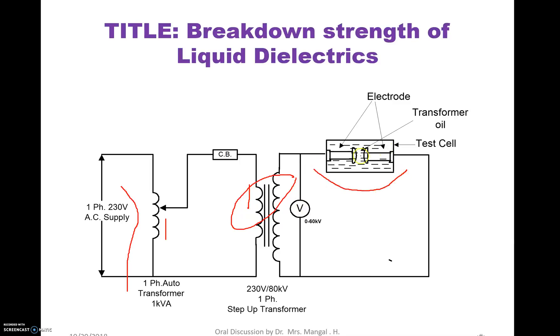Since it is oil, you have to pour the oil into the test cell, which is made of porcelain. The electrodes will be immersed in the test cell and are mushroom-shaped as per Indian standard specifications. Oil must be poured 40 mm above and 40 mm below the electrode. The electrode gap should be 2.5 mm. So all these dimensions you must know. Then the step-up side of the transformer you connect across the electrodes. A voltmeter is shown connected to the secondary side because you need to find out the breakdown voltage, which is the voltage across the electrodes.